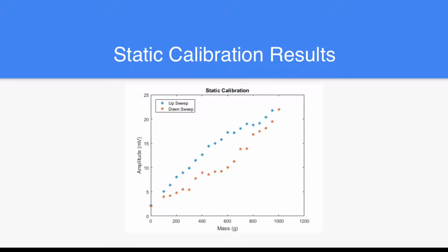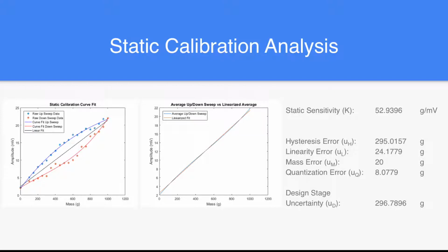In the figure shown is our static calibration raw data. In the blue, you can see the data from the upsweep, and in the orange, you can see the data from the downsweep. To analyze our static calibration data, we then curve fitted a third-order polynomial through the upsweep and through the downsweep data. We also curve fitted a linearized line through the average of the upsweep and the downsweep data. From these results, we were able to get our hysteresis, linearity, mass, and quantization error. From all these errors, we were able to find our overall design stage uncertainty.